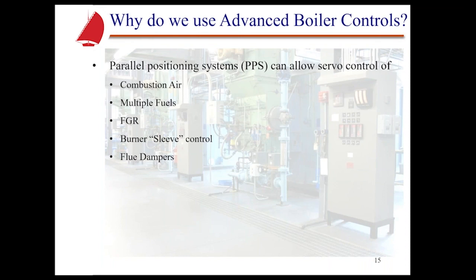Now, our parallel positioning systems, if you look at it, the control could be considered the brains of the system, but the servos are really the hands and feet or the heart of the system, because those servos are actually what really makes this system work. And if they're not operating properly, then that can be a huge, huge problem. I'm going to harp on this because so many times a parallel positioning system will have reliability issues, and it can be tracked right back to how those servos were installed. I can't emphasize enough the couplings that you use, the actual mounting of that servo, those brackets. If those aren't aligned properly, that can be a huge problem. It will not be reliable.